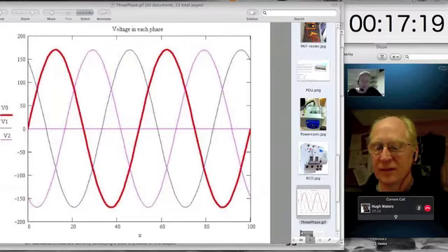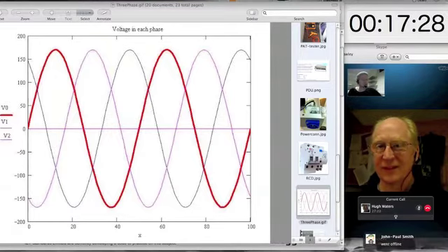And you mentioned you can lose a phase. During a power cut you might have walked out into your street and noticed that maybe only one house in three has its lights turned off. That's because one of the phases has gone. Maybe the red phase has been lost at the substation or further upstream, and so the effect you get there is that one house in three no longer has any power.